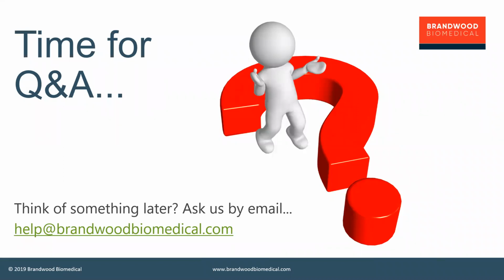As for country to country, that's more about when you're doing the primary testing, when you're testing for the first time. You do need to be aware that some countries have slightly different protocols for things like extraction methods and whatnot. One of those countries being Japan, for example. There's been some interesting work done by some of the experts on the committee. The Japanese variants on the test do seem to be actually a little bit better. So be aware of that when you're going into different markets. Be careful about what the local standards are. Look at the national standards for your market and check that they haven't been modified.